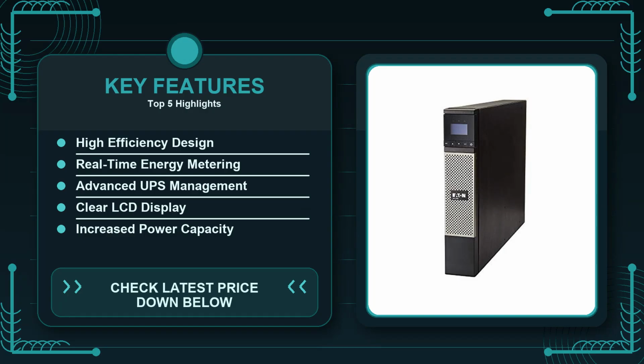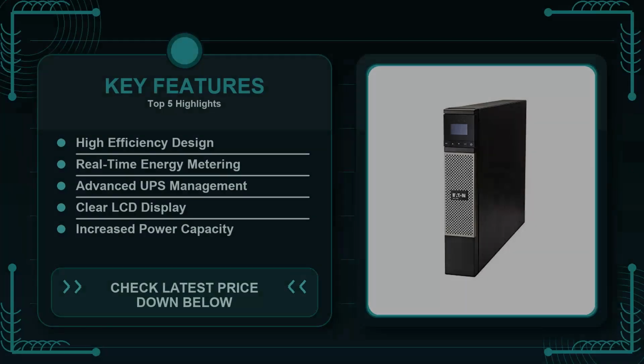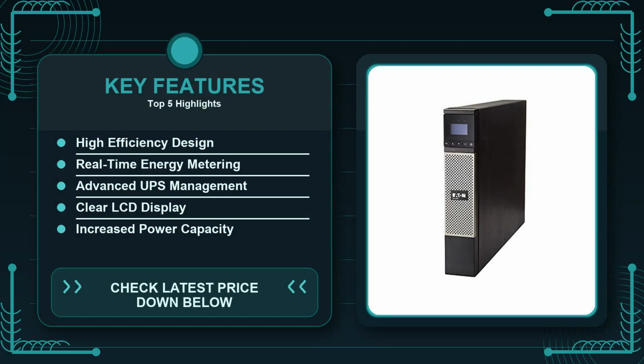On the flip side, there are clear scenarios where you'd be better off looking elsewhere. If you're running a large data center with dozens of kilowatts of load, the 5PX2200RT simply doesn't have the capacity or the modular redundancy you'd expect. Likewise, if you need an extended runtime of several hours to keep critical systems alive while a generator fires up, you'll likely need a larger battery bank or a different UPS architecture. The unit's battery runtime at half load is modest, so it's designed more for bridging brief interruptions than for prolonged outages.